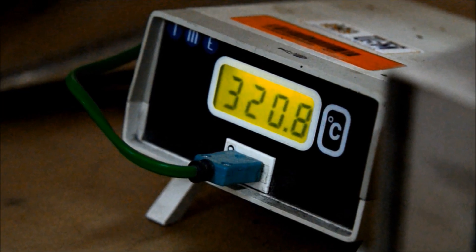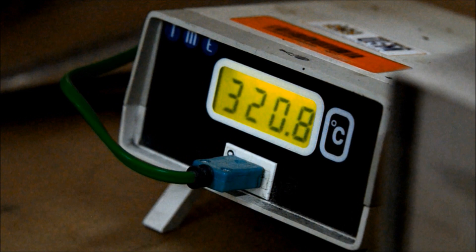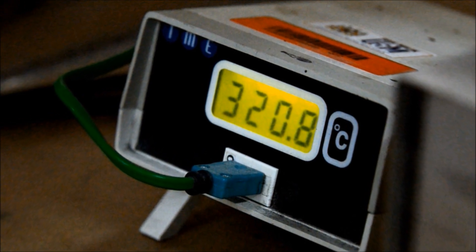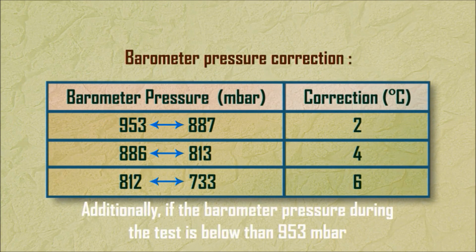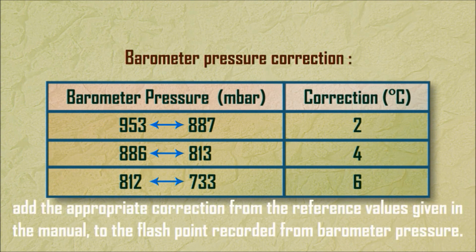Adjust the temperature of the specimen as needed. Additionally, if the barometric pressure during the test is below 953 mbar, add the appropriate correction from the reference values given in the manual to the flashpoint recorded from barometric pressure.